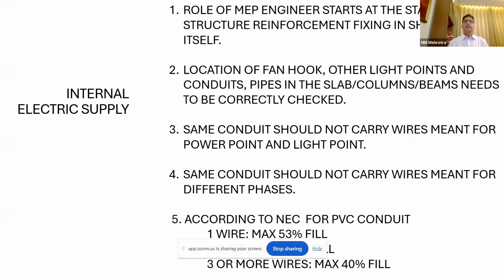Now, an MEP engineer is required to reach the site when structural reinforcement is being fixed, at the shuttering stage itself. Why? Because the fan hook will be connected to that reinforcement. Once the cement has set, that fan hook cannot be placed. If it is placed, it will weaken the structure. So it has to be done that way. Then there will be conduits which are required to be buried inside the concrete. They will be placed, and there will be crossings. We have to take care how my conduits are crossing. These are PVC crossings. Is any iron sleeve required around that? Those things we are required to see.